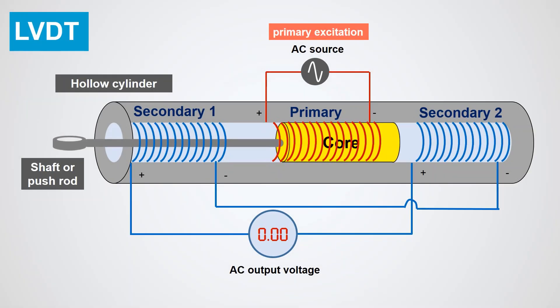But as soon as the core moves by even the smallest amount, a differential voltage is induced at the secondary output. The phase of the output voltage is determined by the direction of the core's displacement, while the amplitude is determined more or less linearly by the magnitude of the core's displacement from the center.